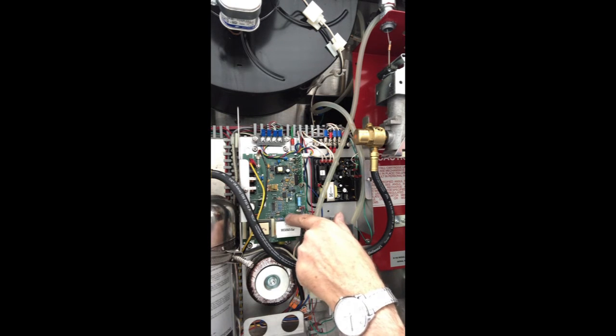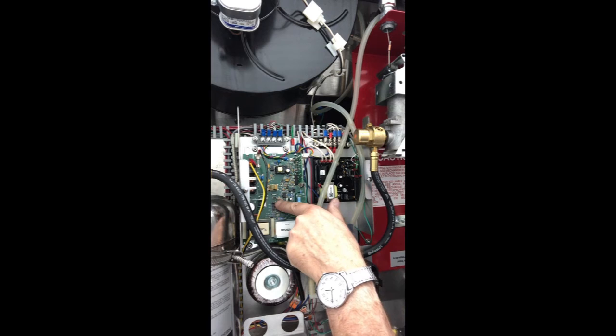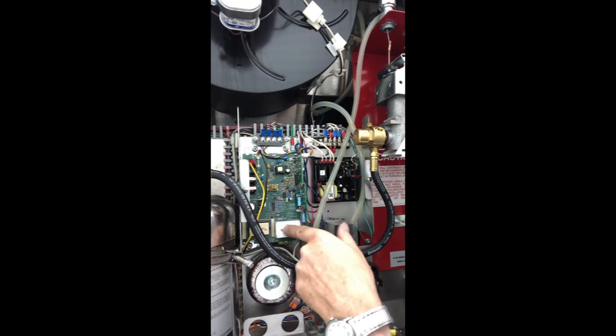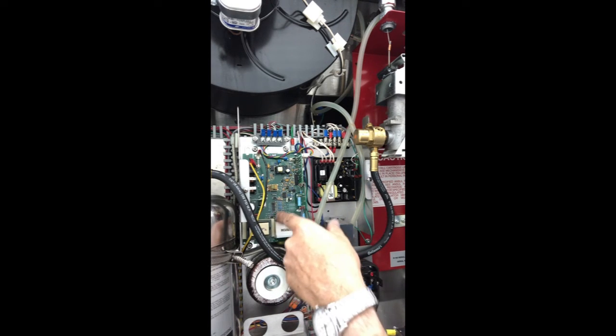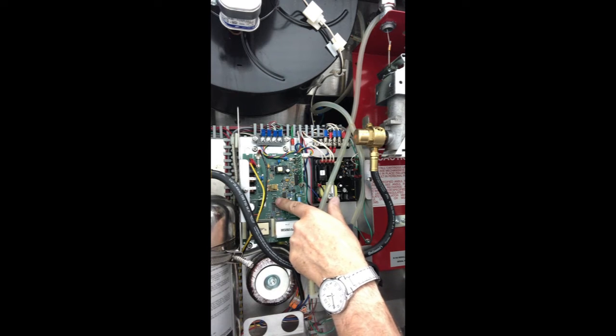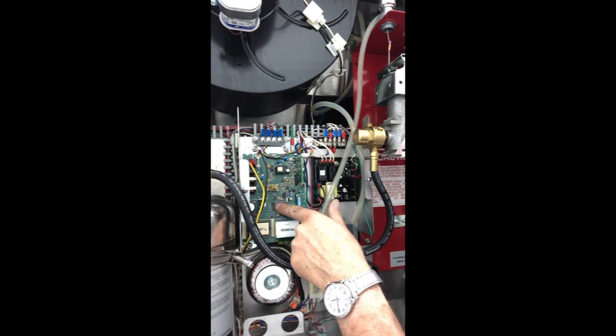You'll notice on this board that we have a little jumper set right here. Go right over to the end of here, right up to the center. At the very top is 2.1 microamps. That's where we want to have that pinned at. Sometimes on the older units, you'll find them down here. Move those up to 2.1.